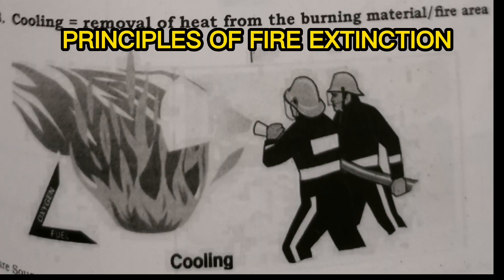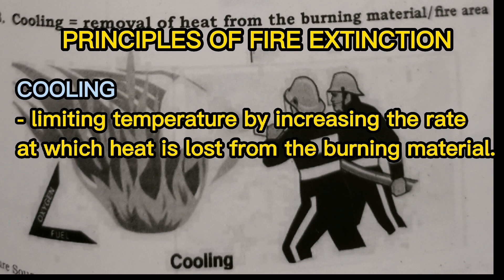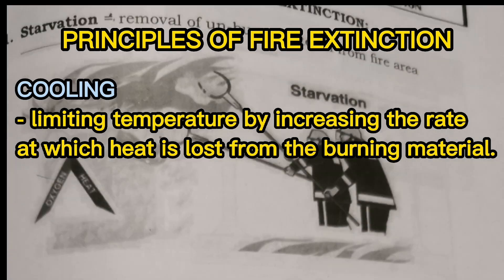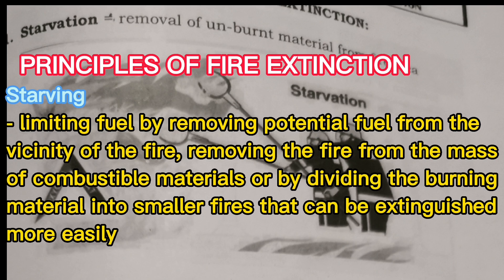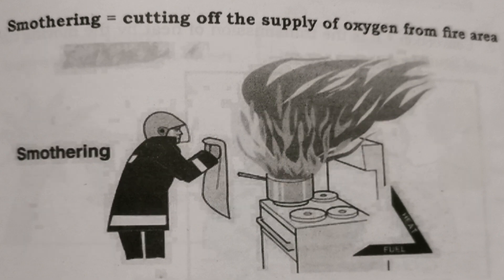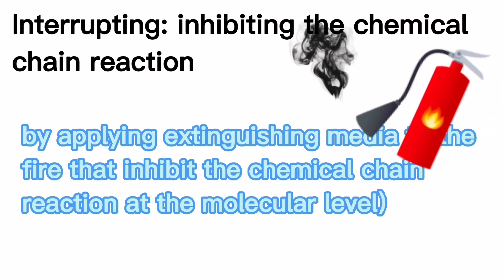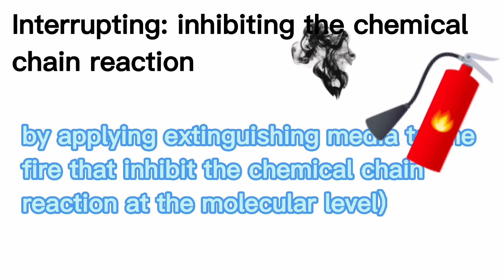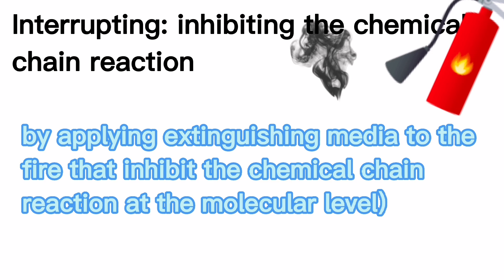Principles of fire extinction: Cooling — limiting temperature by increasing the rate at which heat is lost from the burning material. Starving — limiting fuel by removing potential fuel from the vicinity of the fire, removing the fire from the mass of combustible materials, or dividing the burning material into smaller fires that can be extinguished more easily. Smothering — limiting oxygen by preventing air from reaching the seat of the fire, allowing the combustion process to reduce the oxygen content in the confined atmosphere until it extinguishes itself. Interrupting — inhibiting the chemical chain reaction by applying extinguishing media to the fire that inhibit the chemical chain reaction at the molecular level.